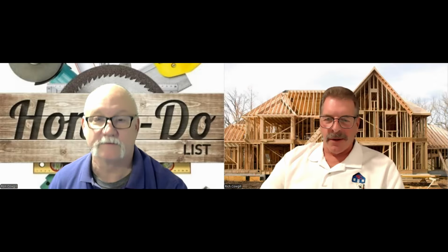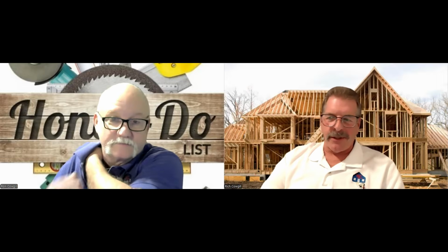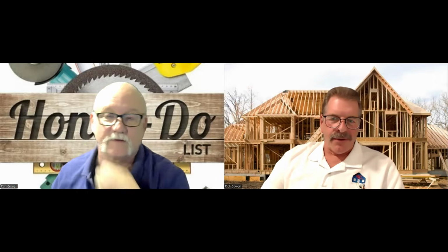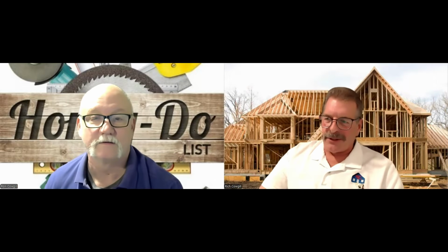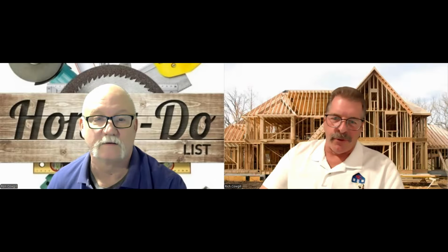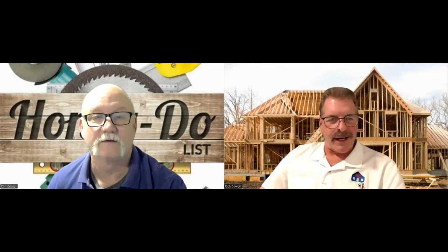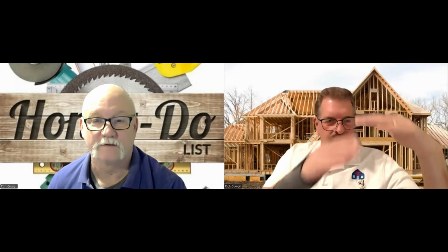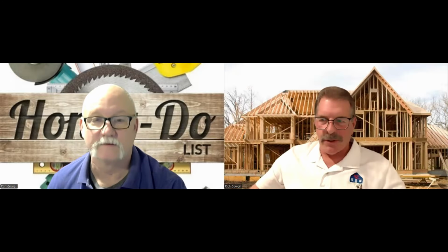So what they did on this particular house is it's done the exact same way as this. Those attics at both ends were not cut off from that floor structure running from one side of the house to the other. They did the same thing. Truss joists, framed the lower ceilings to make details, which left a plenum ceiling from one side of the house to the other, which just allowed the air.